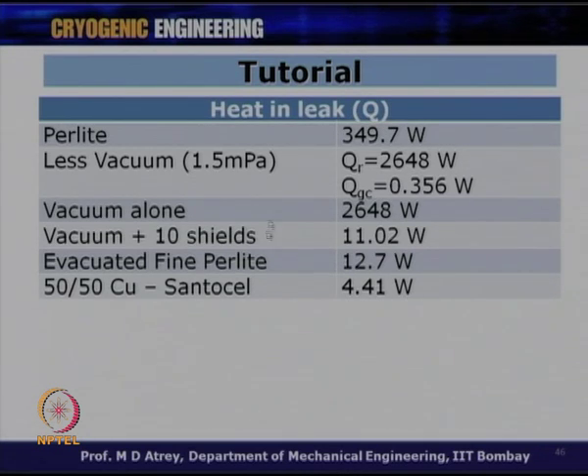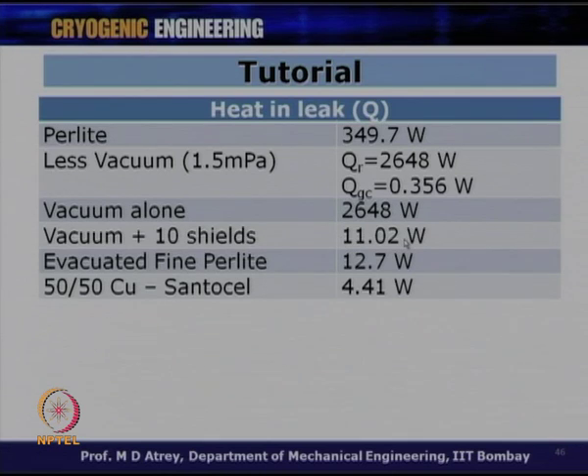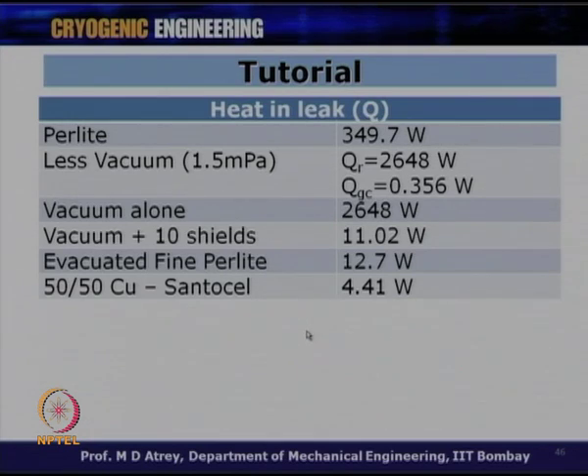Comparing all results: perlite (gas-filled) = 349.7 W, vacuum alone ≈ 2648 W, vacuum + 10 shields = 11 W, evacuated fine perlite = 12.7 W, Cu - Santocel = 4.41 W. While 10 shields in vacuum gives a similar result to evacuated powder, the practical difficulties of manufacturing and weight increase make evacuated and opacified powder more preferred solutions.